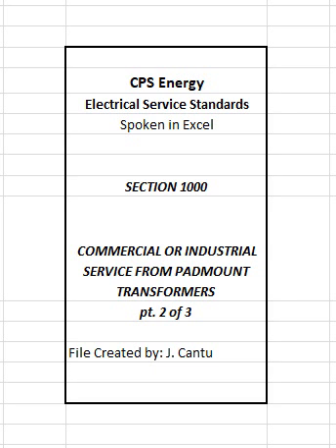C. Load side conduits. The standard installation requires the use of Schedule 40 or 80 PVC conduits. CPS Energy will specify and limit the size and number of conduits and the manner in which they exit the transformer's secondary compartment. Conduits are required to exit at the bottom of the transformer through the slab. The maximum number of conduits shall not exceed 10 4-inch conduits or 8 5-inch conduits, refer to Table 1003. Conduits shall not exit the top or side of a transformer. Exception: wireways installed with tap box installations shall meet the minimum requirements outlined in D below.